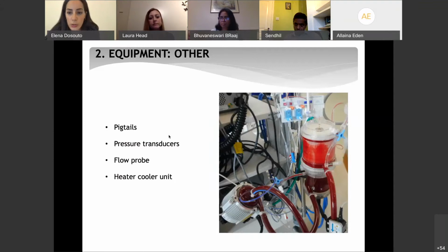Our pressure transducers, so they are located in here and here. So this one, the bottom, is what we call P1, and it's pre-membrane. So this one will tell you the pressure that the blood has to overcome to pass through the oxygenator. So it's really relevant to tell you how the fibers in the oxygenator are coping. And this one is post-oxygenator, and we call it P2. So this one tends to give you more information of the patient, what happens after the oxygenator. So for example, if your line is clamped, this will give you information. And we also monitor the difference between these pressures, and this is what we call the gradient, and it's always displayed on the screen.